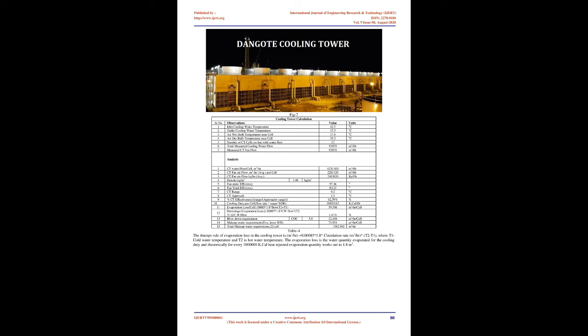Condition of equipment. At the time of test the equipment was in good condition, with particular attention to the following. 1. Water distribution system was clear and free of foreign materials which may clog or impede the normal water flow. 2. Mechanical equipment was in good working order, with fans adjusted for proper rotation and uniform angle that will yield within +/-10% of the specified horsepower loading. 3. Drift eliminators were clear and free of algae and other deposits which may impede normal air flow. 4. Filling was free of foreign materials such as oil, tar, scale, or algae. 5. Water level in cold water basin was at normal operating elevation and maintained substantially constant during the test.